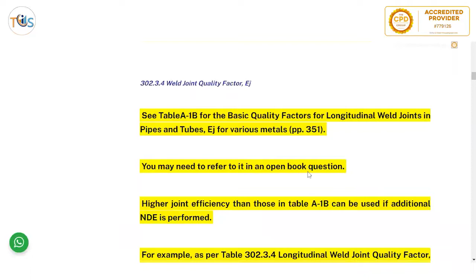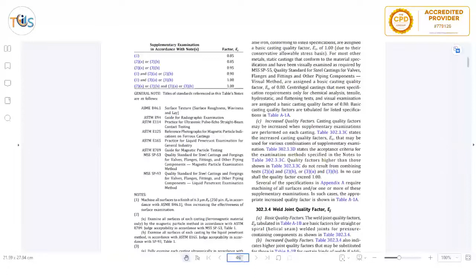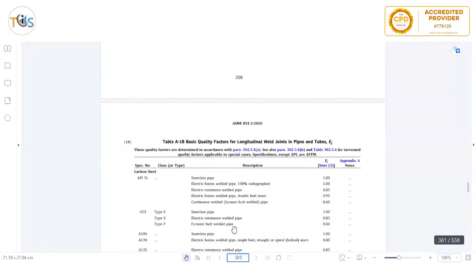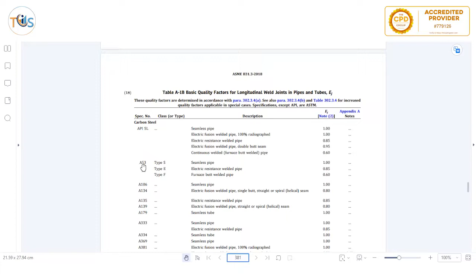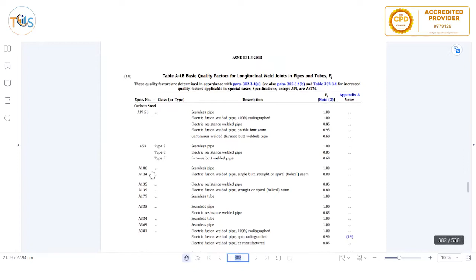For the weld joint quality factor, you need to go to page 351. Now let's go to page 351. It tells you the basic quality factor for longitudinal weld joints in pipes and tubes. So if it's a seamless pipe in carbon steel made according to API 5L, then EJ is 1. And if we say A53 grade, it's a seamless pipe, again it's 1. So A106, you have to look for it and see the weld quality factor. Whereas on page 350, it's the same thing, but for casting quality factor.